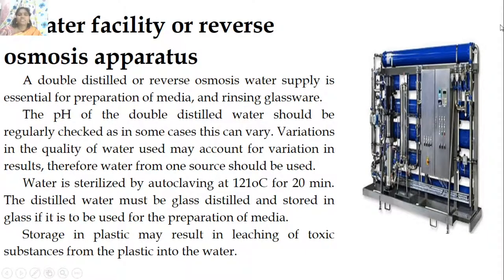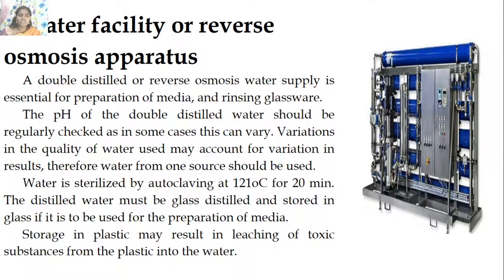Water facility: a double distilled reverse osmosis water supply is essential for preparation of media and rinsing glassware. The pH of the double distilled water should be regularly checked, as variations in water quality can account for variation in results, so water from one source should be used. Water is sterilized by autoclaving at 121 degrees for 20 minutes. Distilled water must be glass-distilled and stored in glass, as storage in plastic may result in leaching of toxic substances into the water.